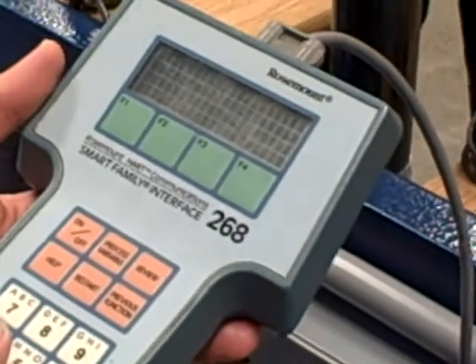Yep, start. Okay, alright. So we are firing up the Rosemount 268 HART communicator. We're going to do a trim on the sensor of this transmitter. It's a Rosemount 3051.